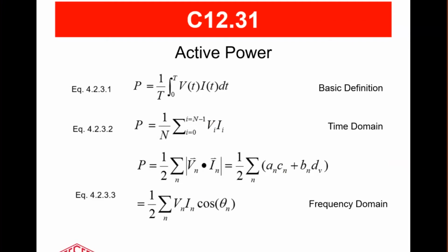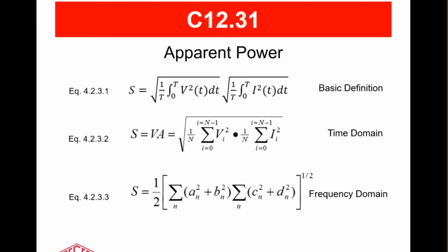Okay? And then when we get to the apparent power, here's where things get very interesting, because once you have harmonics, the power triangle breaks down. It simply doesn't work in the world of harmonics.